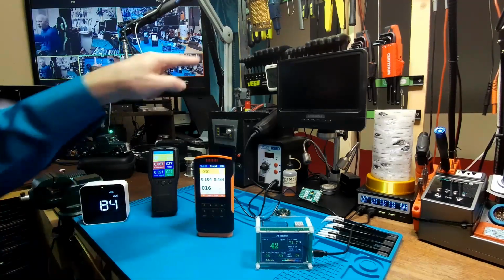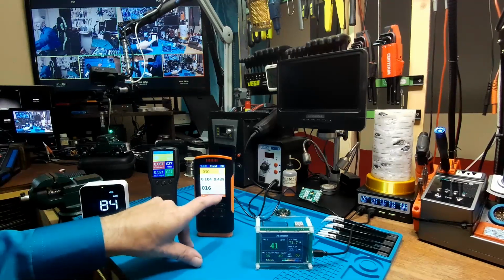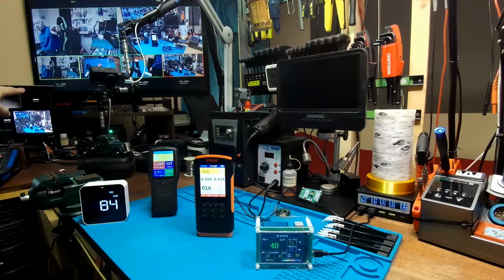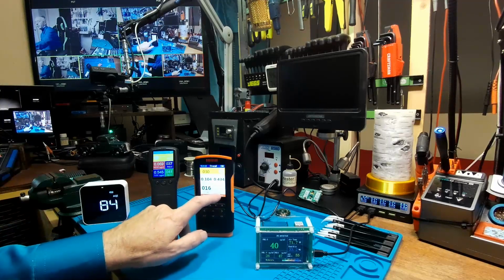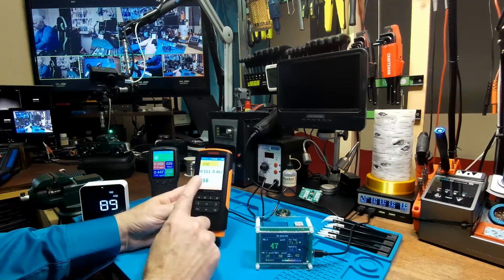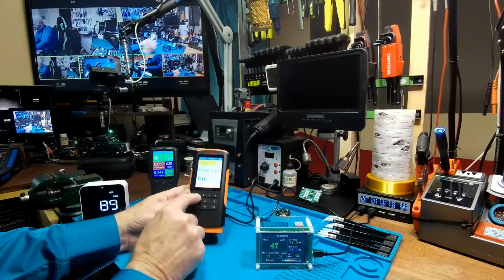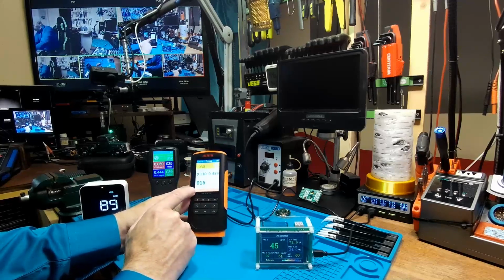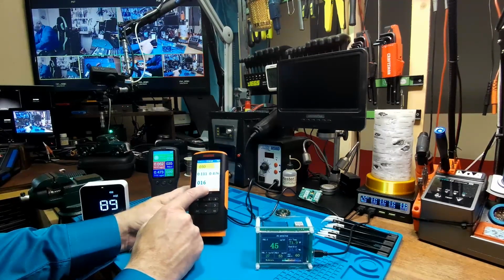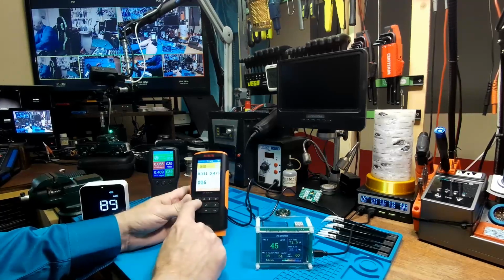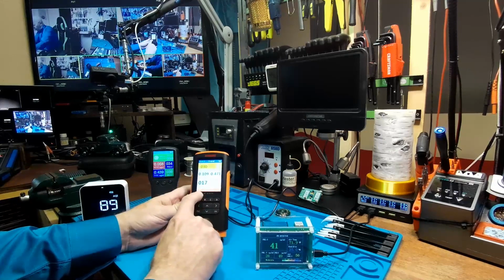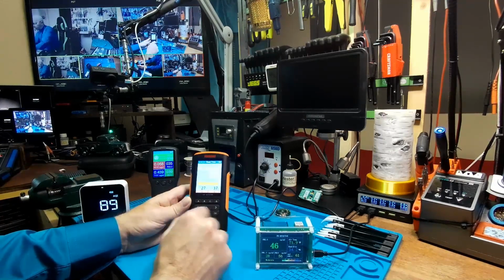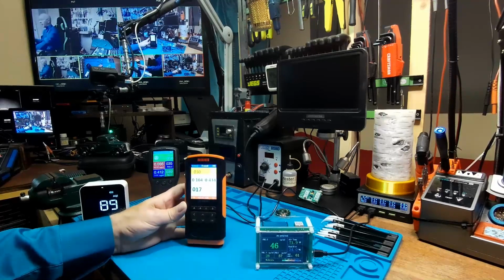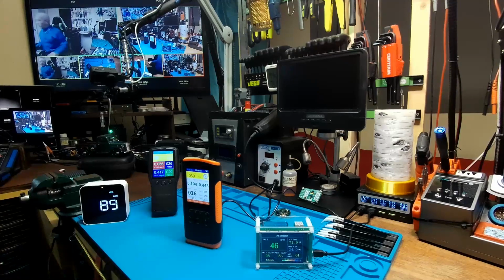I have a humidity sensor up there that says 26. This says 24. And then my one over there says 25. So that's pretty cool. So that's working pretty well. Now it has a real-time function in it, and you press the A button because you have your menu options here for real-time RT, recording your data, calibrating the unit, and setting the unit settings. And that corresponds with A, B, C, or D. Real-time is A, and I think instead of continuing this right here with this camera, I'm going to move to the overhead camera, my bench camera, and do the rest of this video.